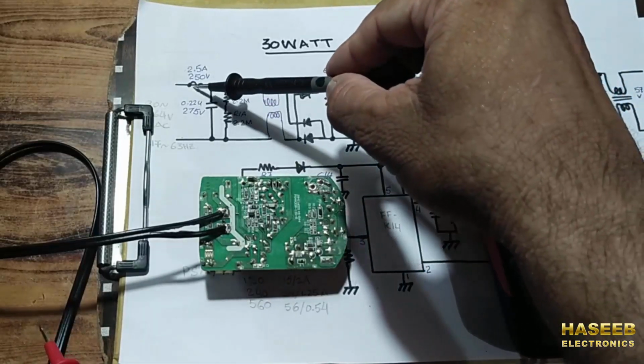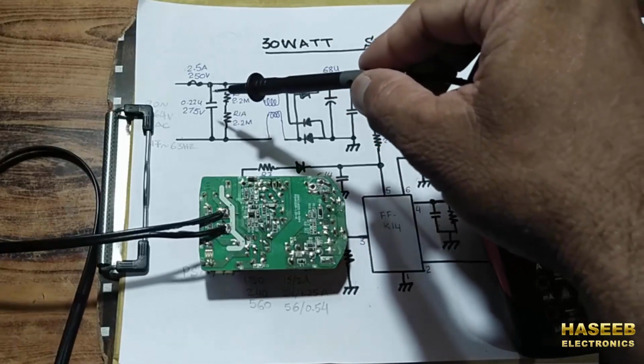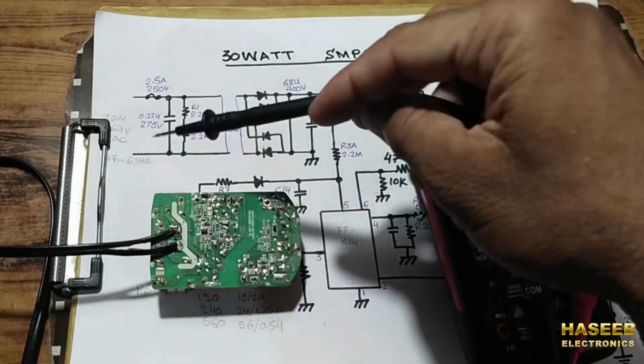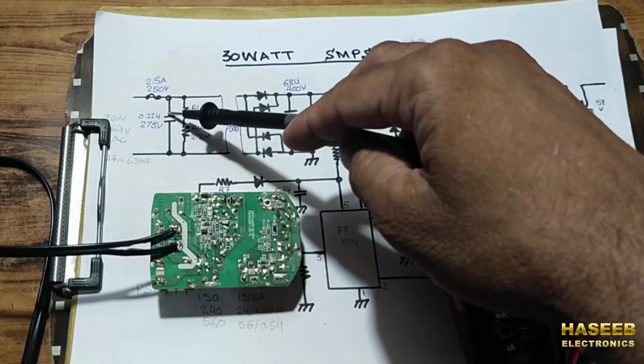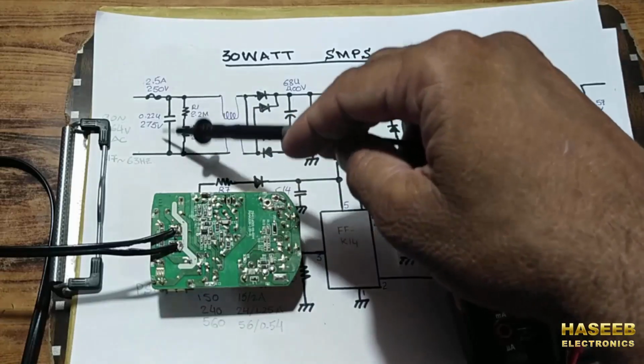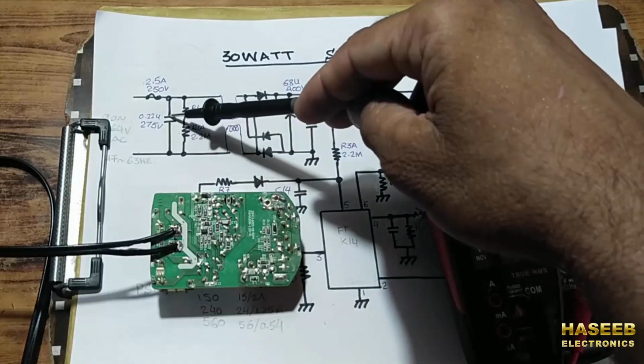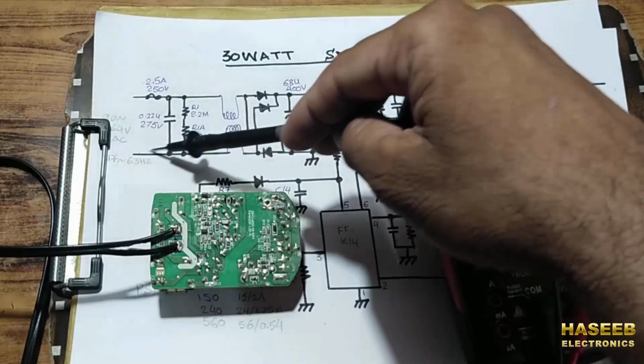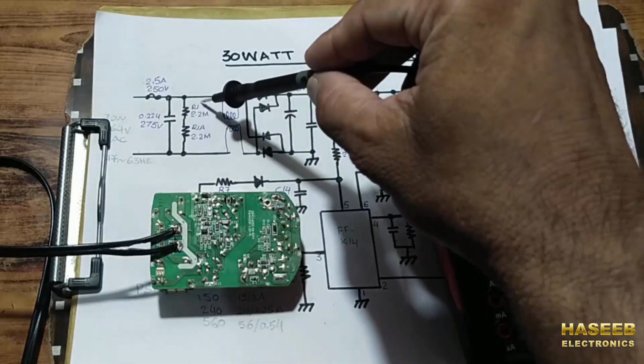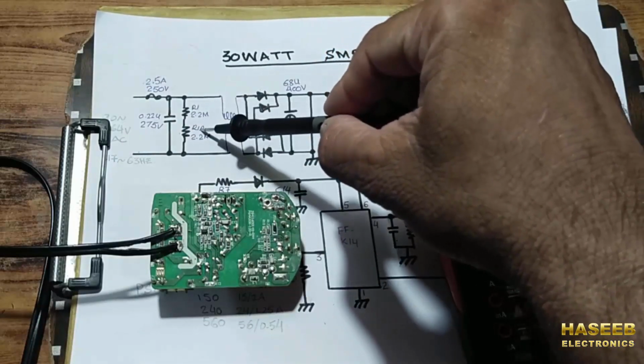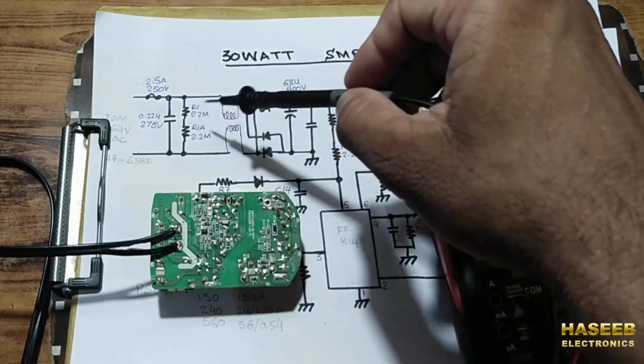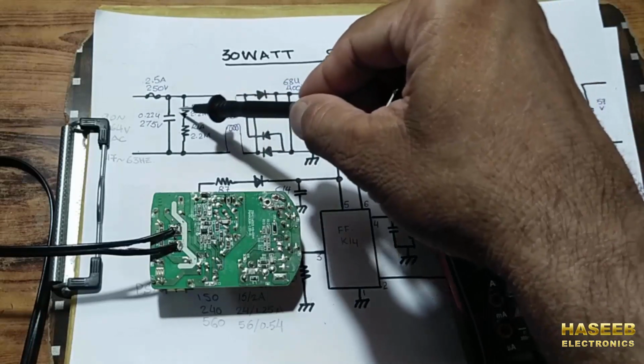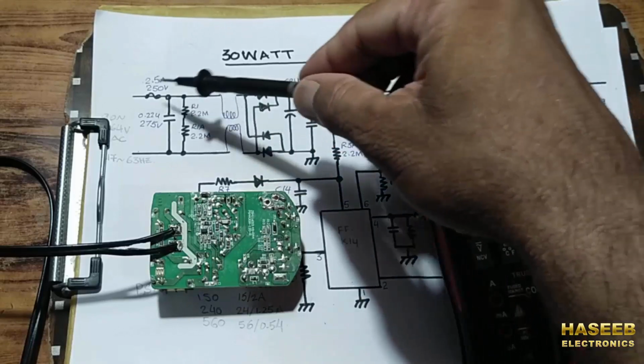Sometimes our fuse burns out again and again. The first cause, most of the time, is maybe this capacitor: if it is short circuit, it will pass electrical current from this point, this way, and it will damage the fuse. Or maybe we have a voltage arrestor here, an MOV or anything; a short circuit in the parallel line can damage the fuse.